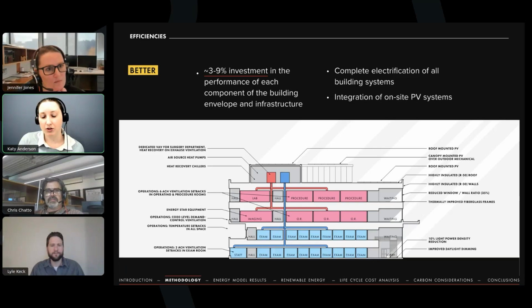Similarly, in the surgery program, we can segregate the imaging and the OR sections. The OR section is segregated so that the rest of the surgery program can have a lower filtration requirement, which reduces the fan power required, and it also allows overnight shutdowns in the non-OR section, because the ORs are required to have those high airflow requirements overnight. In addition to that, we have included operational setbacks overnight. In the ORs, they can go down from the required sort of 20 air changes per hour to 6. So that's a big decrease, and that's not a cost add, but it is a big operational change that is very beneficial. And we've also included some temperature setbacks.